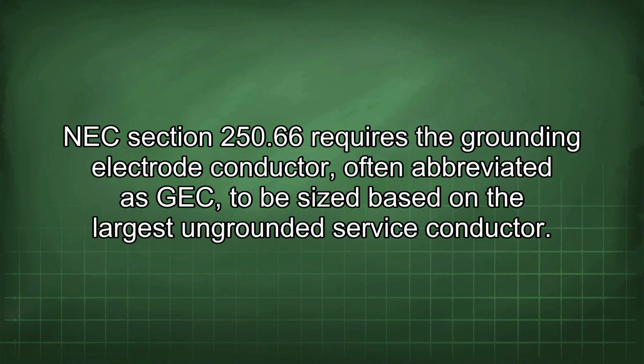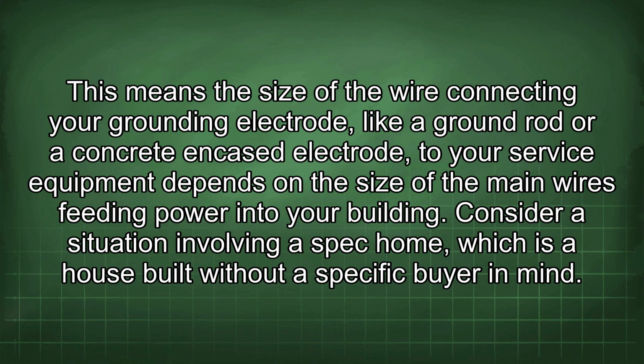NEC section 250.66 requires the grounding electrode conductor, often abbreviated as GEC, to be sized based on the largest ungrounded service conductor. This means the size of the wire connecting your grounding electrode, like a ground rod or concrete encased electrode, to your service equipment depends on the size of the main wires feeding power into your building.